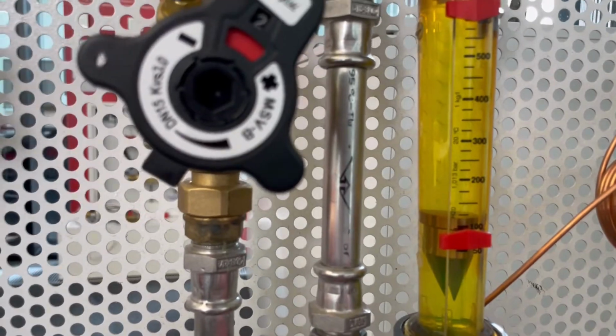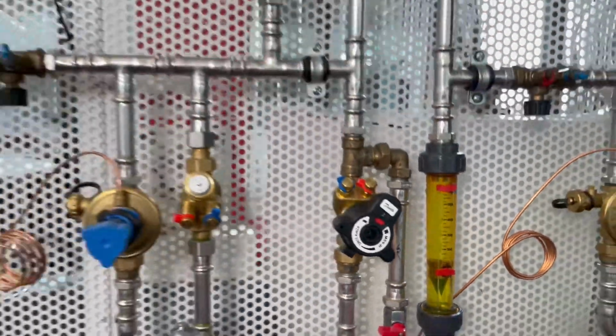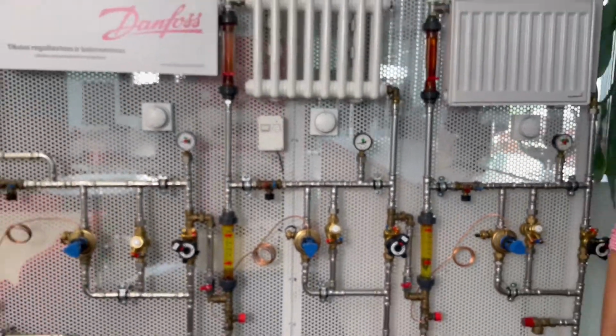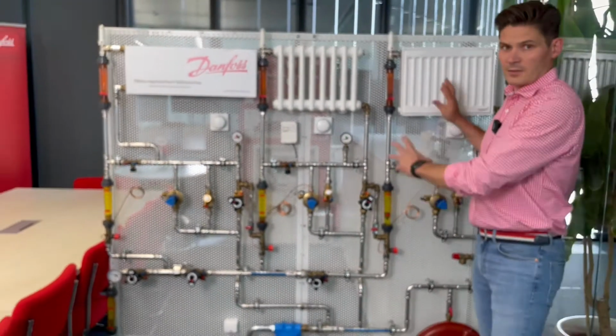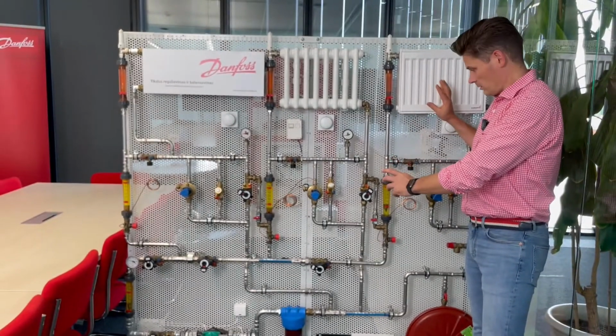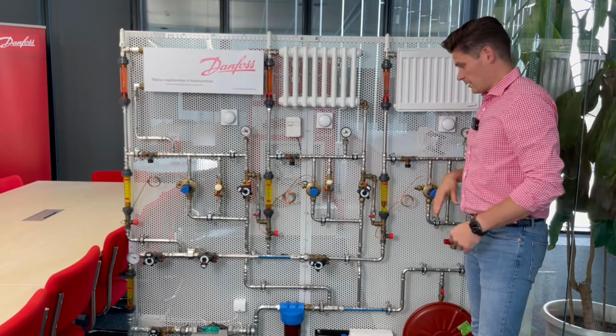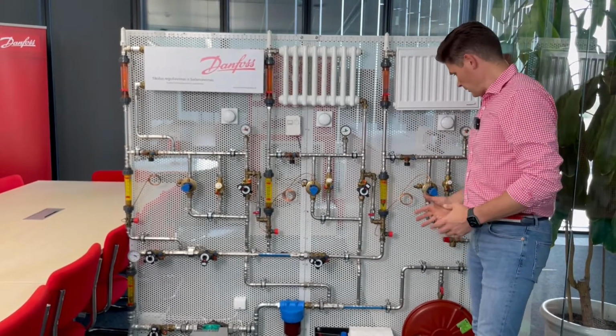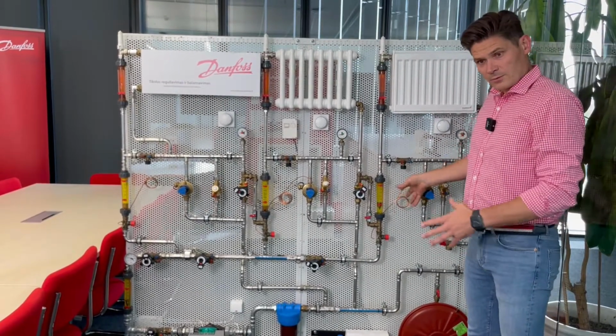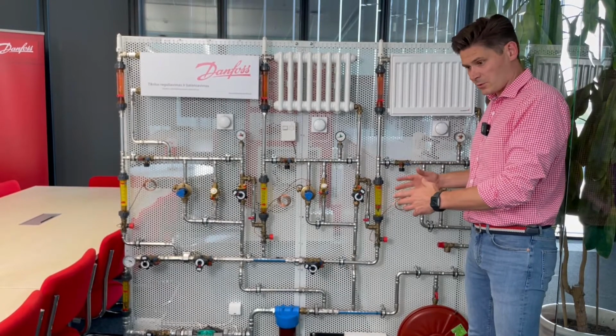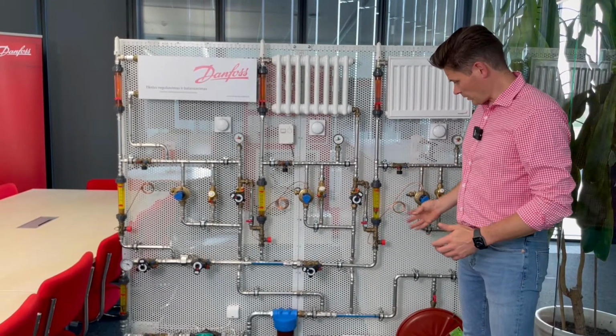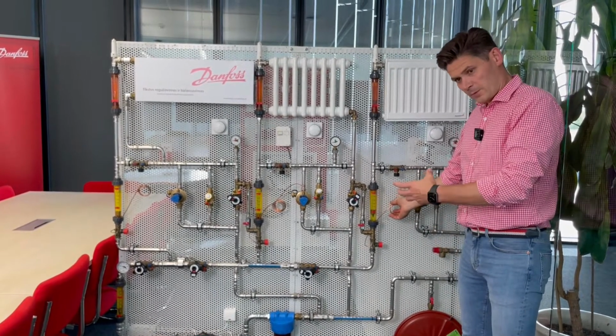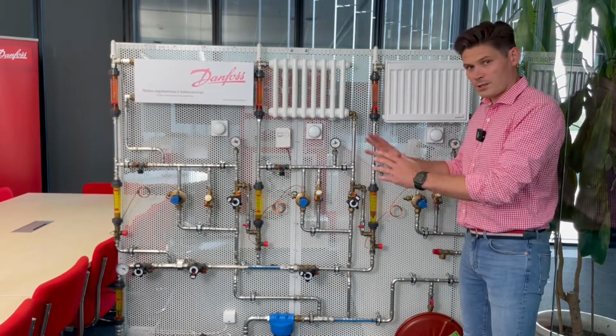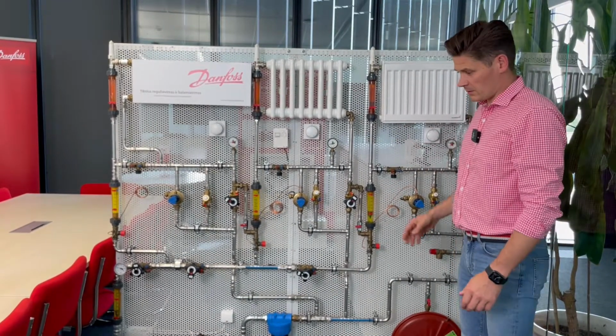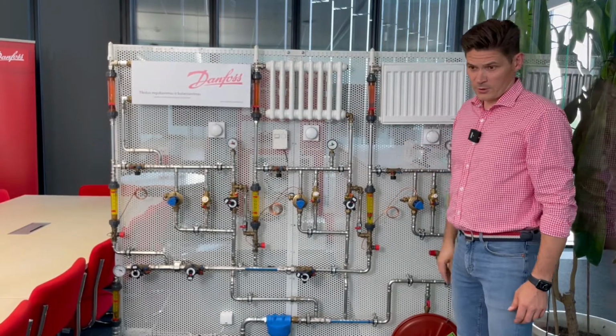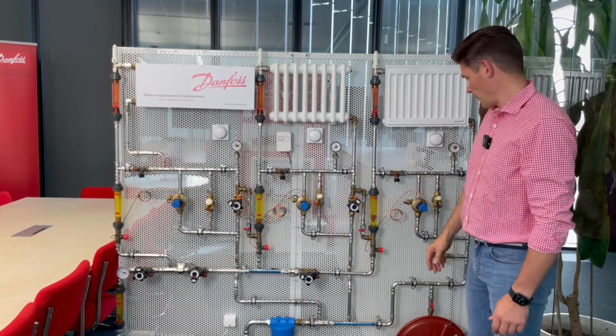So it doesn't matter if somebody plays in a substation with a circulation pump, you will never have too much flow on your riser, or it doesn't matter if you have an automatic balancing valve on your apartment. If it is a manifold system, it might be that you have a pressure controller on your apartment, so you are fully independent of all your neighbors and fully independent from your substation circulation pump.